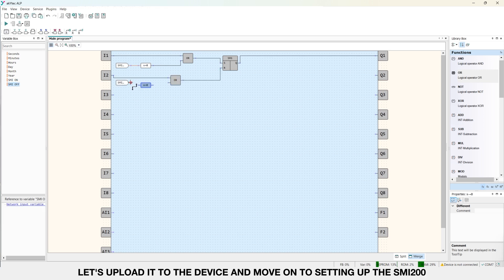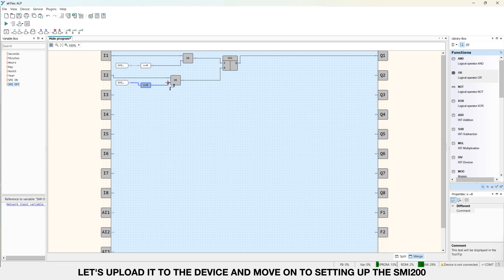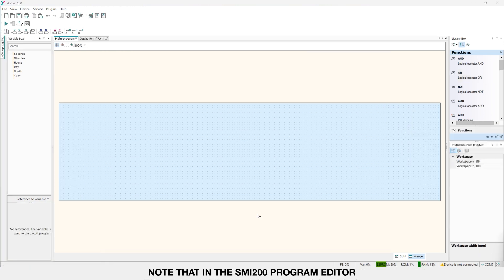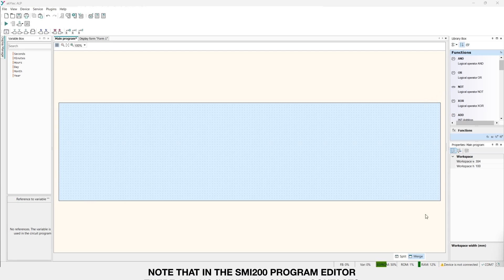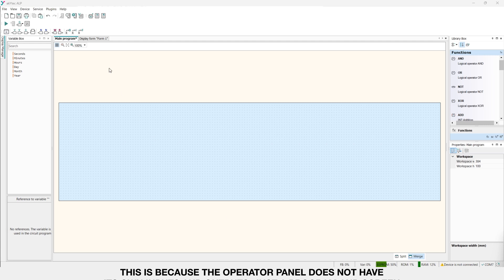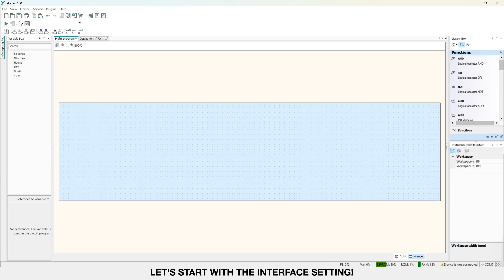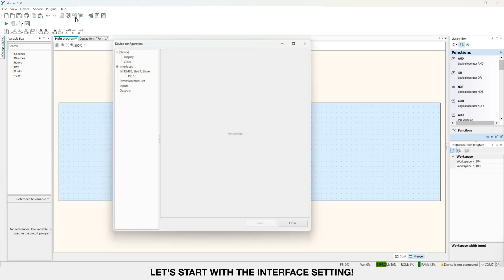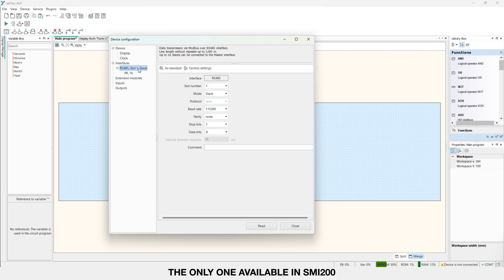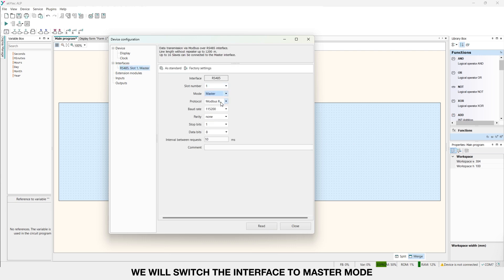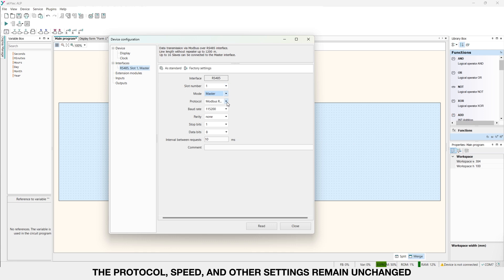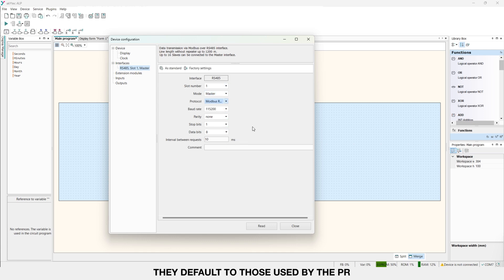Note that in the SMI200 program editor there are no input and output contacts. This is because the operator panel does not have its own inputs and outputs. Just a program and screen. Let's start with the interface setting. The only one available in SMI200. We will switch the interface to master mode. The protocol, speed and other settings remain unchanged. They default to those used by the PR.